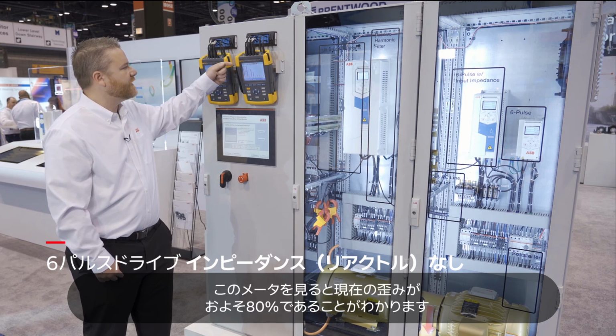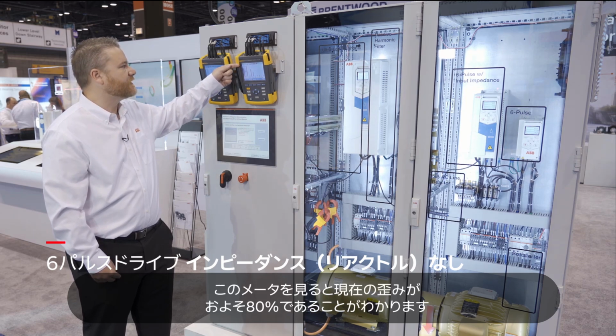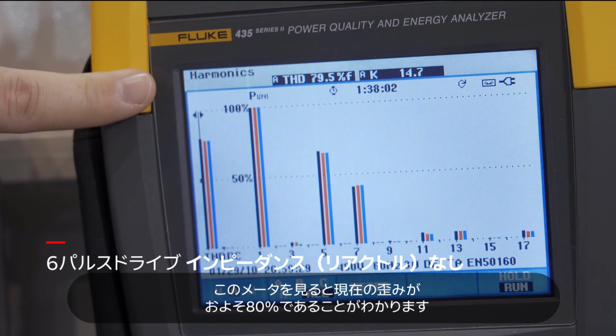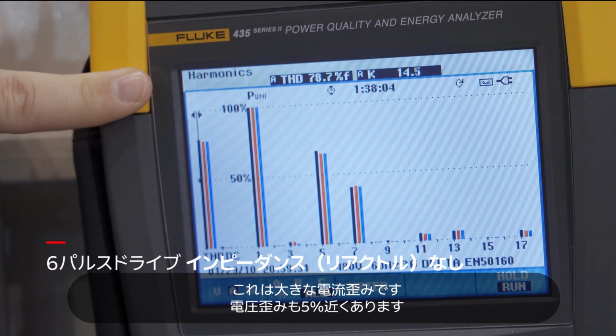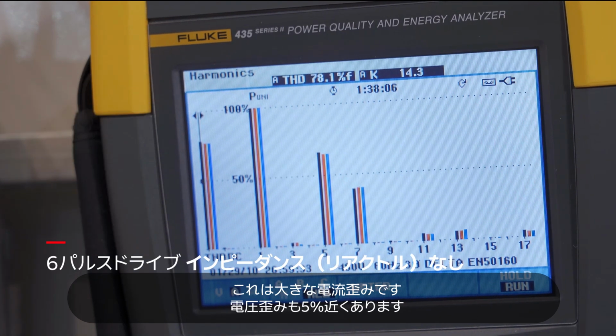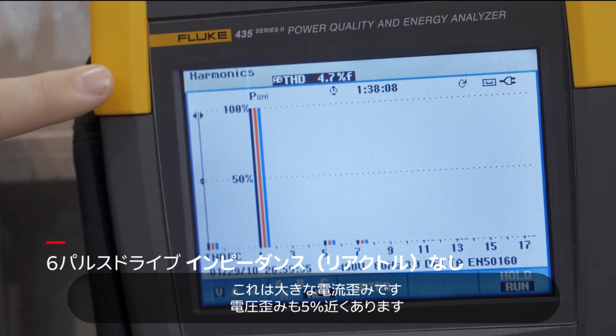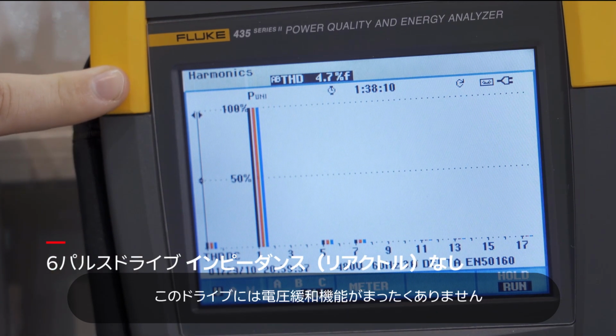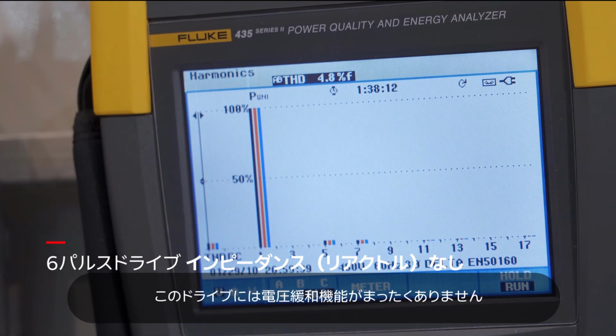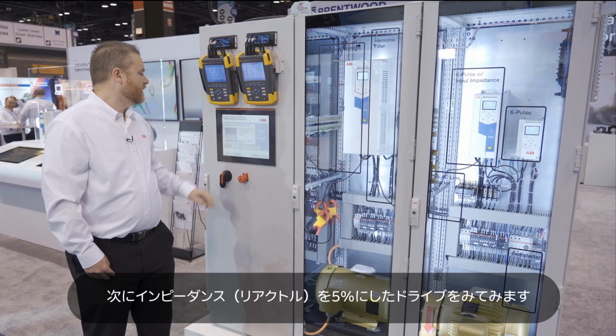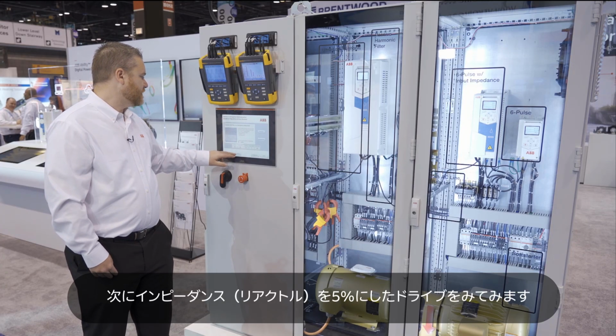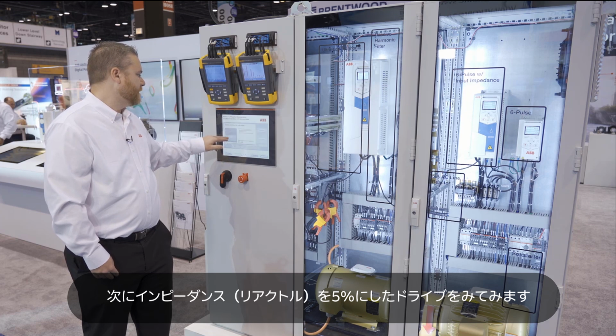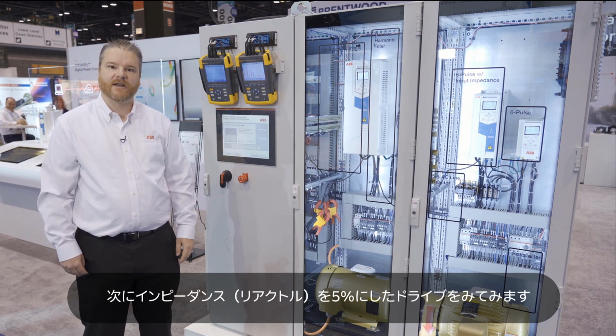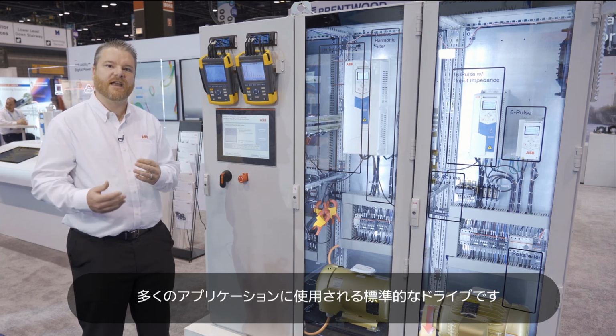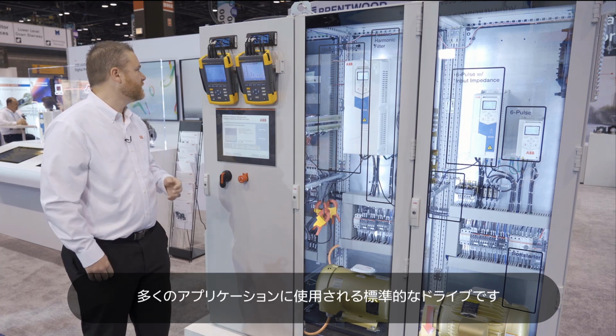So I'm going to come over to this meter right here, and you can see that the current distortion is almost 80%. So this is a considerable amount of current distortion. And I can look at voltage distortion, which is nearly 5%. So again, a considerable amount of voltage distortion. That drive has no harmonic mitigation at all. What I'm going to do next is move over to a drive with 5% impedance harmonic mitigation in it. So this is kind of your standard drive that a lot of applications will use.